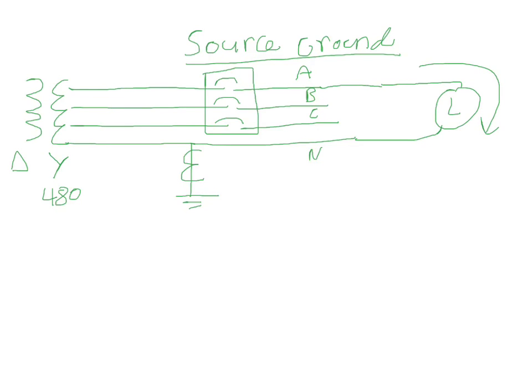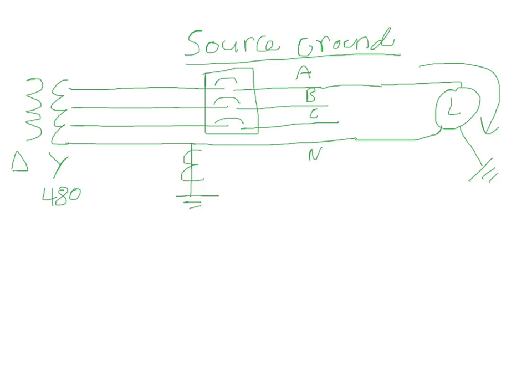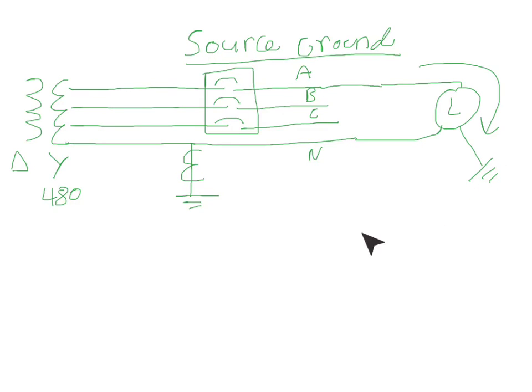Now say there was a ground fault on this load here. So what would happen is it would go to ground, and the current is always going to return to the source. The source here is going to be the transformer. So if there was a ground fault on our load, the current would come back this way through ground. It would come through ground and come up on the ground bar here.